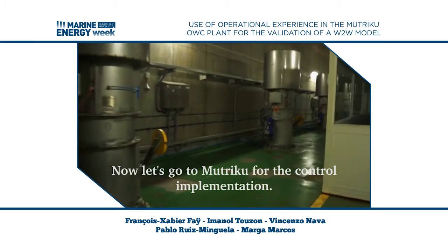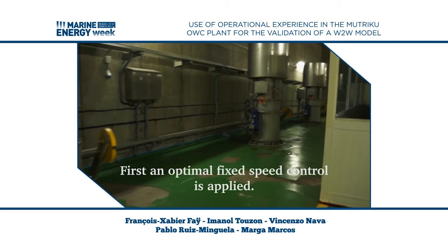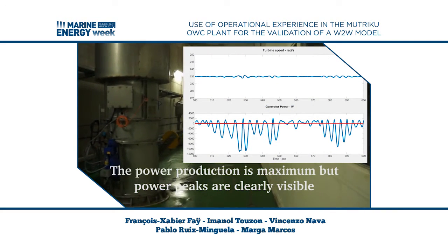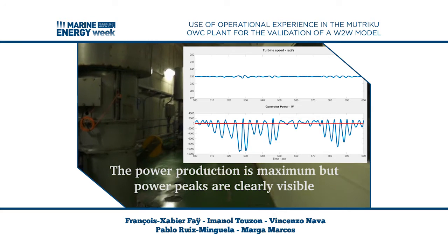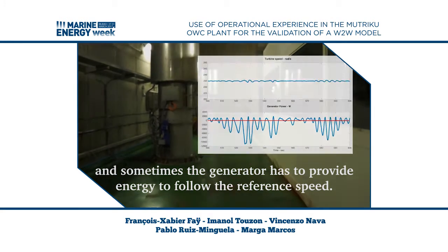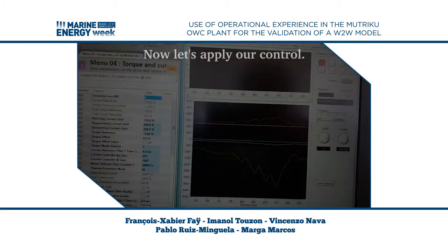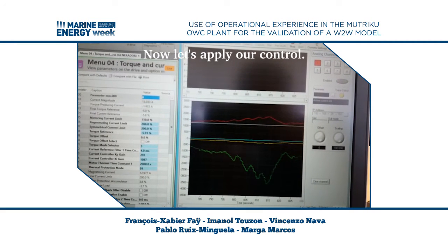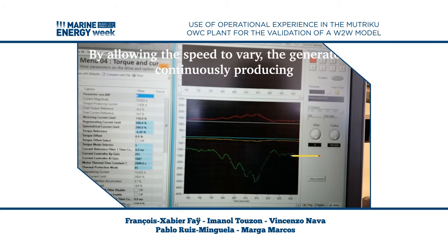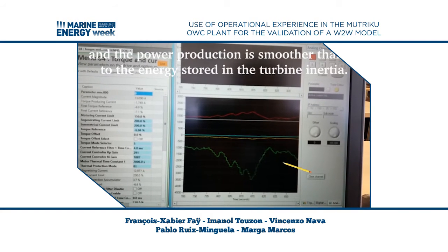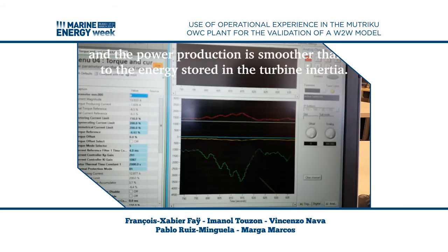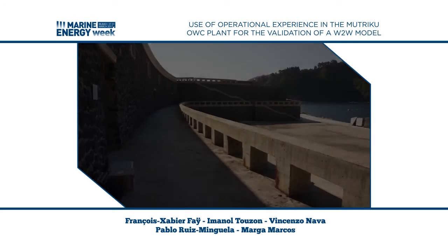Now let's go to Mutriku for the control implementation. First, an optimal fixed speed control is applied. The power production is maximum, but power peaks are clearly visible, and sometimes the generator has to provide energy to follow the reference speed. Now let's apply our control. By allowing the speed to vary, the generator is continuously producing and the power production is smoother, thanks to the energy stored in the turbine inertia.